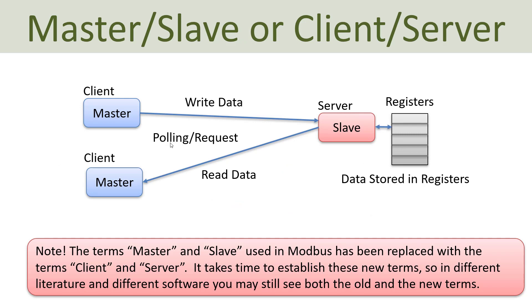Note that originally the terms master and slave were used, but slave has been replaced by the term server, and master has been replaced by the word client. Basically, we can have one or more servers that are storing the Modbus data in so-called registers, and then we can have different clients that are writing data to the server or reading data from the server.